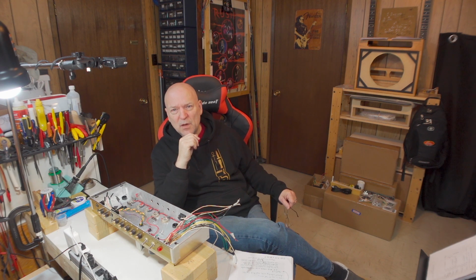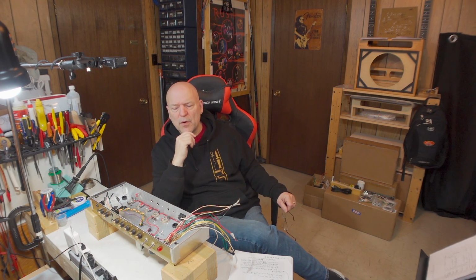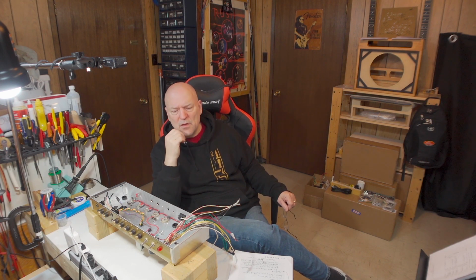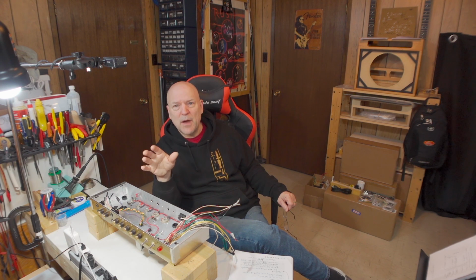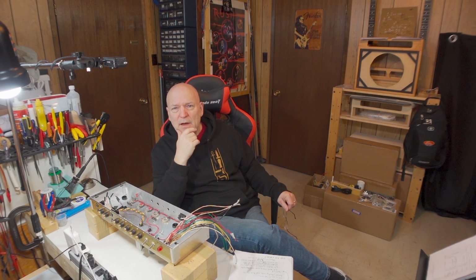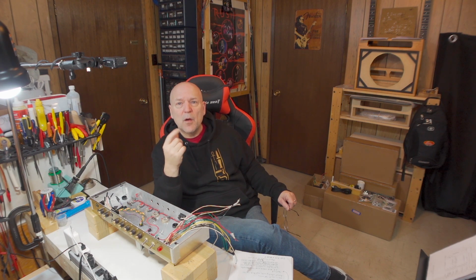When you talk about things shorting, arcing, or burning, an outright short that causes a burn usually means a dead power transformer. This one had a light brown spot, it was hot, and I could hear it arcing. It may not be damaged to the point of not operating, but that arcing creates a carbon path wherever it arcs, and the more it arcs, the more conductive that path becomes.